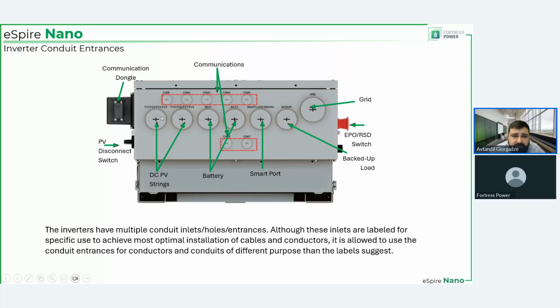What matters to us is that the conductors are grouped together in conduits properly, following the NEC code, and that all the conductors end up at the appropriate ports or terminals. Then, the communication dongle on the left side goes to the bottom. There are 4 screws to secure it in place. You have a PV disconnect switch. Again, this is not a rapid shutdown activation switch. It's a PV disconnect switch, so high voltage still exists. The EPO RSD switch is actually what activates the RSD and also prevents power flows as needed, so that once you press it, it goes to an emergency power off. It remains online, but some of the circuits are offline and the RSD is activated.